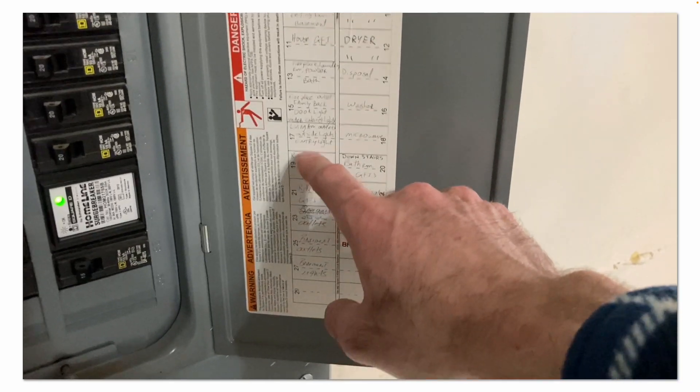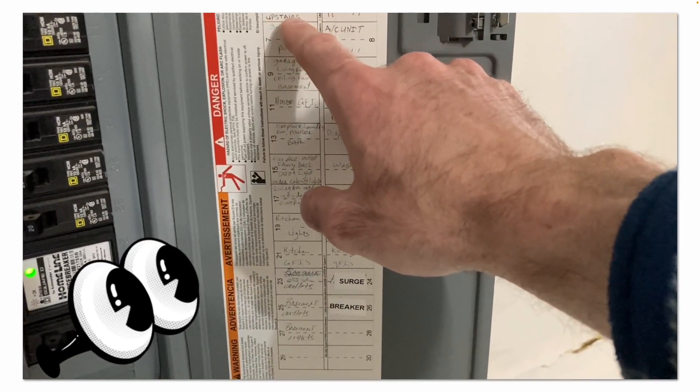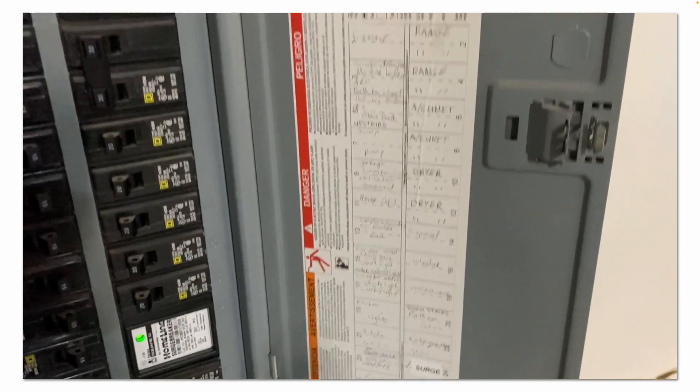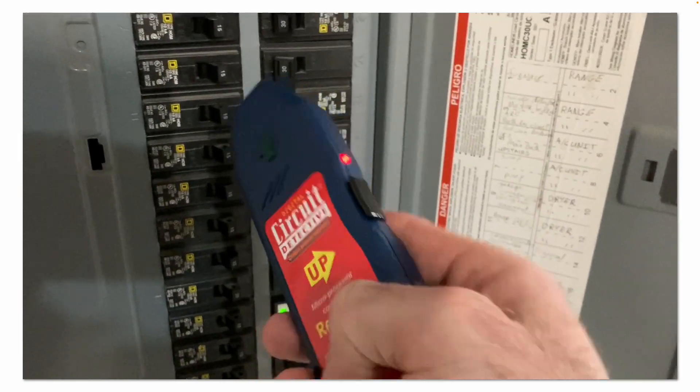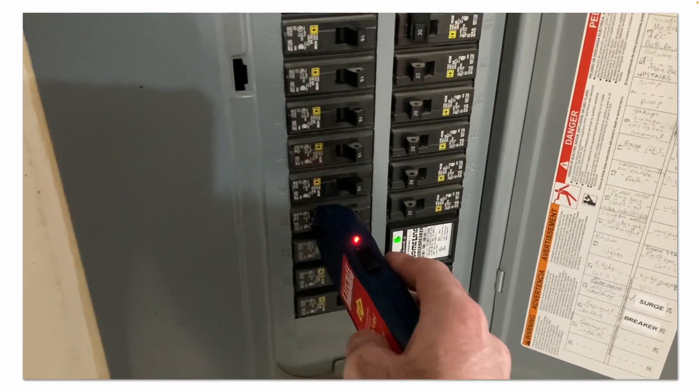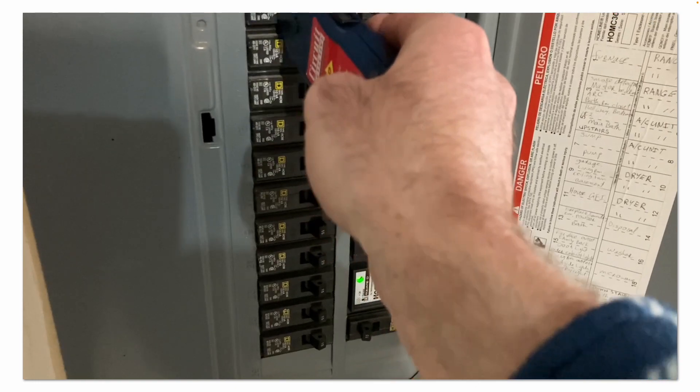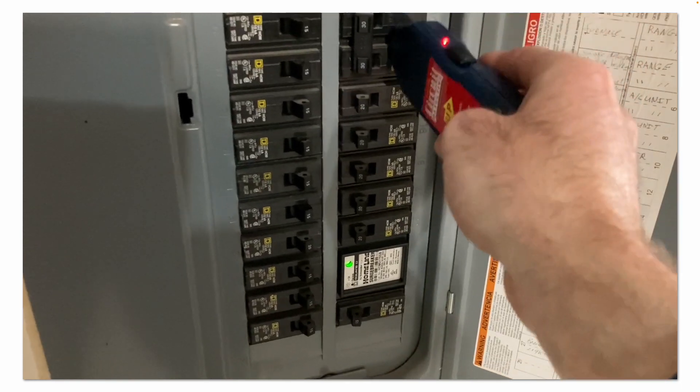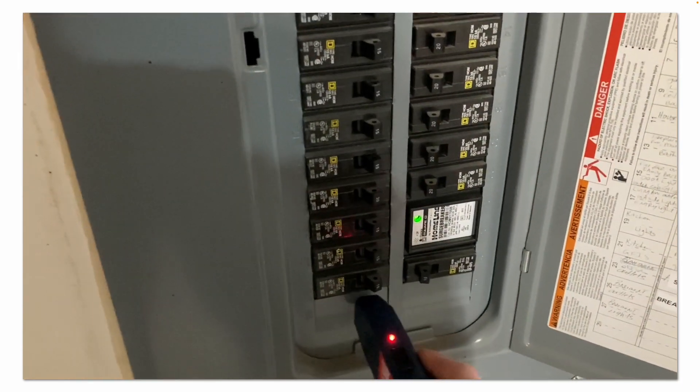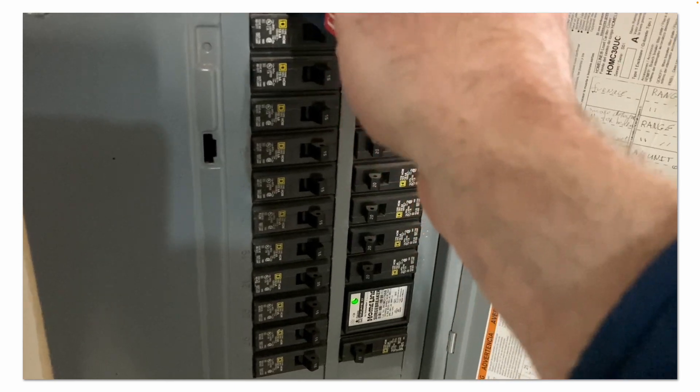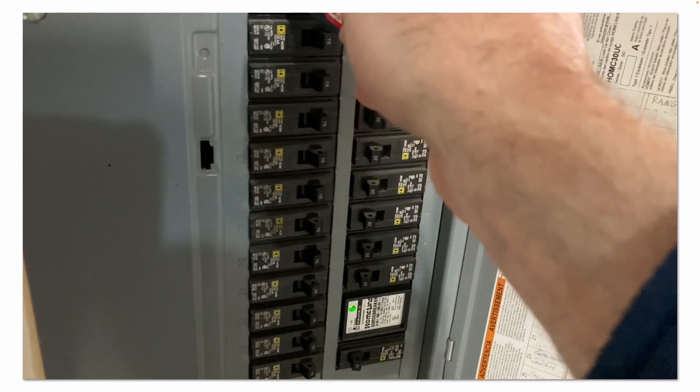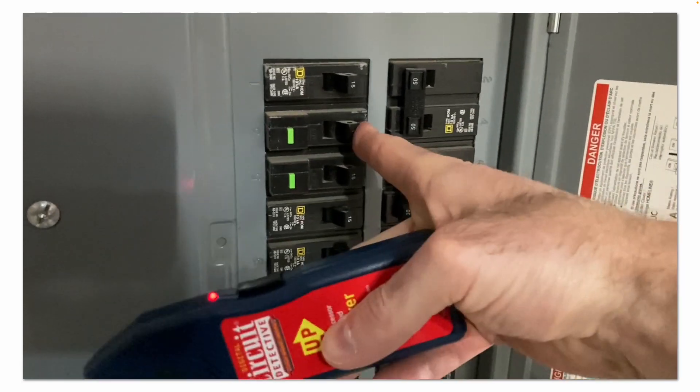So I'm just going to see if I see anything that says upstairs master bathroom, master bedroom. It could be three or five. We'll use our receiver, turn it on, it's powered up, and I scan the entire panel twice. You can see the arrow pointing up, so that end of the device needs to be pointing up, and the receiver will flash and blink when it finds the proper breaker. So again I'm going around a second time. Right about there, yep.